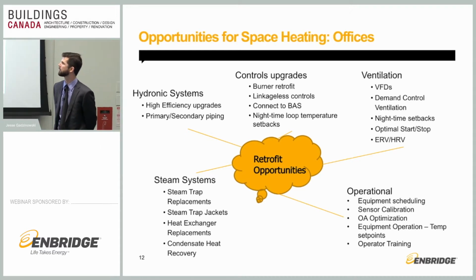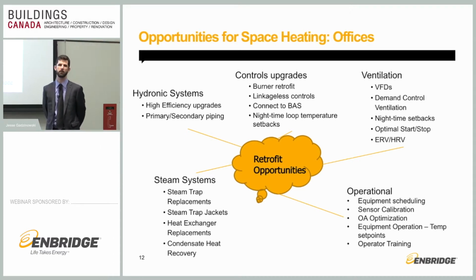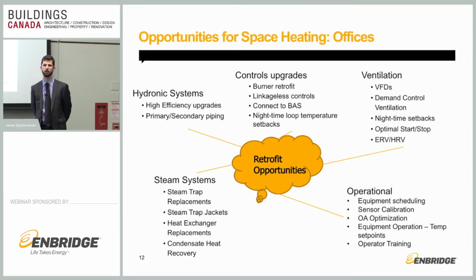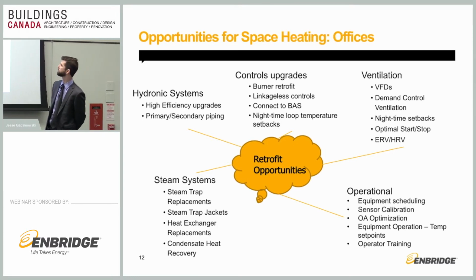System upgrades in terms of piping, a lot of the times we're seeing in the field that some older systems still have that primary direct return system where all of the hot water is being pumped through the boiler, and the boiler essentially acts as a big radiator. So a good upgrade for these types of systems is simply going to a primary, secondary, or an intermittent pumping situation where you're limiting that heat loss in the boiler systems.